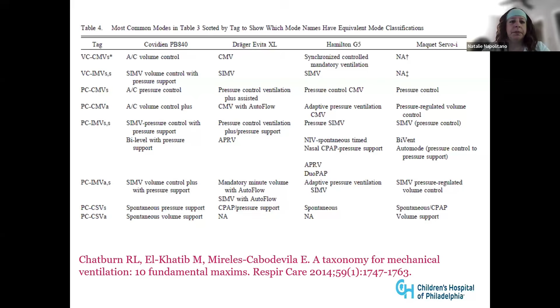So when looking at transport ventilators versus ICU ventilators, there are some differences in how they function. Most transport ventilators are turbine driven because we want that longer battery life. We want to only have one gas source to be carrying around with us. And most of the ICU ventilators are compressed gas driven, where they have both medical grade air and oxygen at high pressures going into the machine. And they need a constant power source. Most of them don't have but a 45-minute to an hour battery. Some of them have hot swappable batteries that you can put in them if you want to be able to transport on them, but that is actually rare.